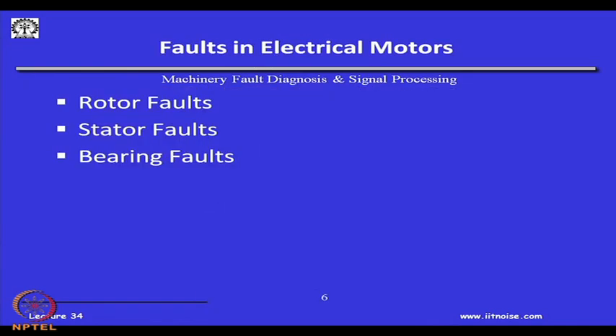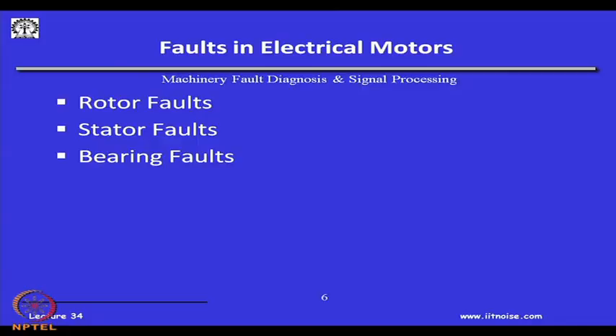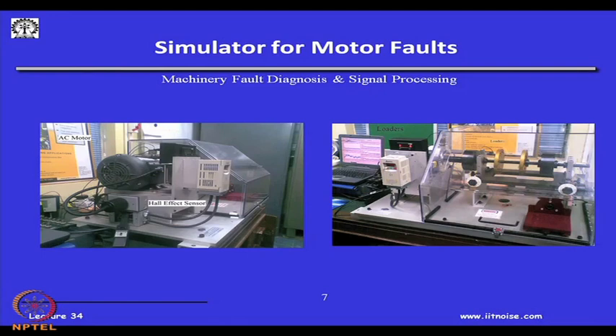So, with this kind of a background about electrical motors, as you know, now rotors can have faults, stators can have faults, and the bearings of the motor, obviously, they can have faults, and you know how to find out the fault in bearings. So, what we did in our laboratory, okay, we have a motor which is driving a mechanical unit. This is the rotor which is supported on two bearings, and we are now concerned with this motor.